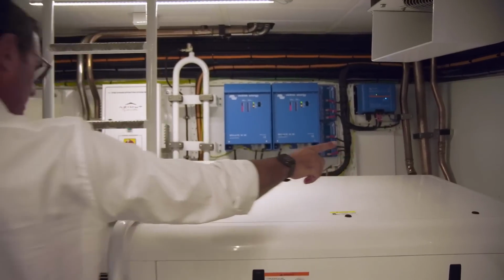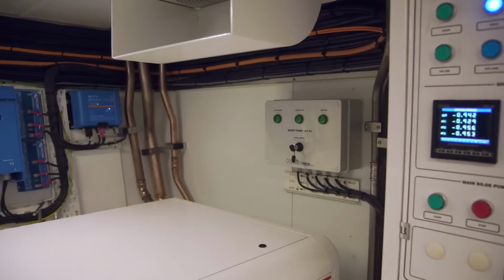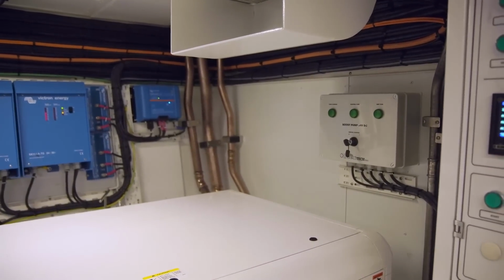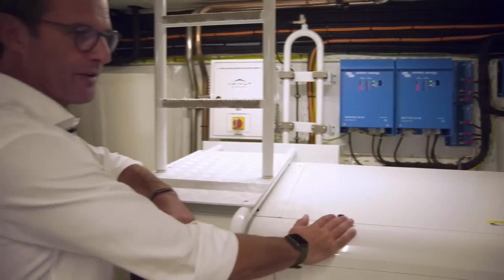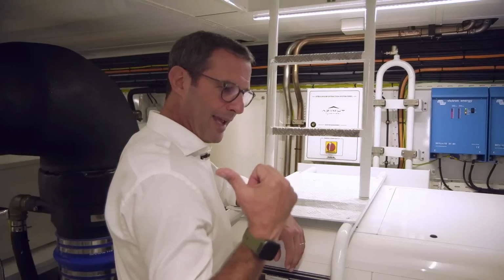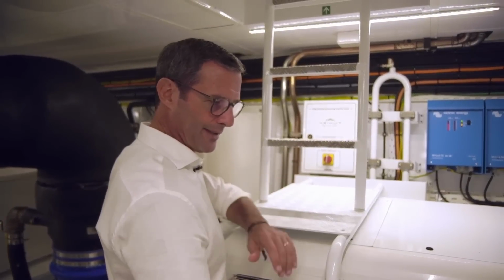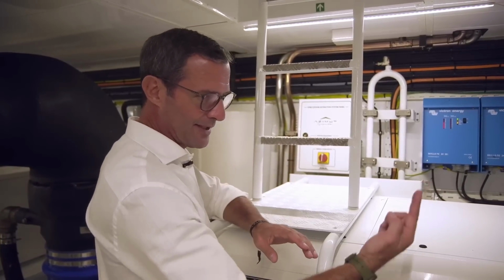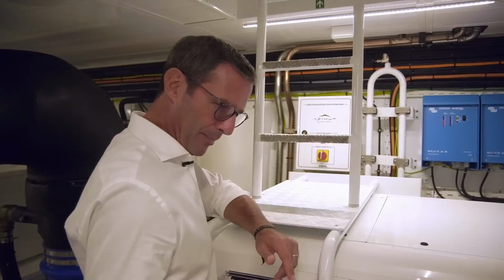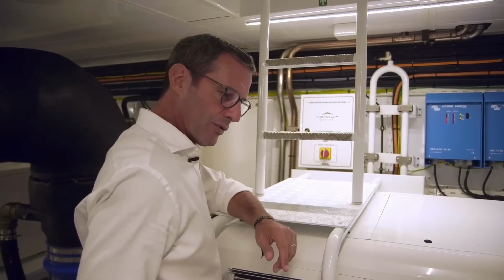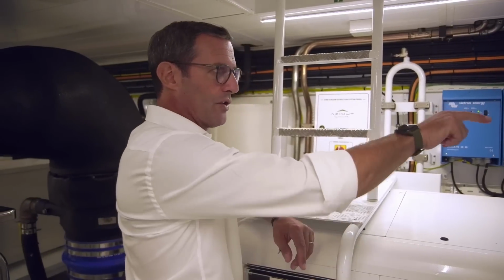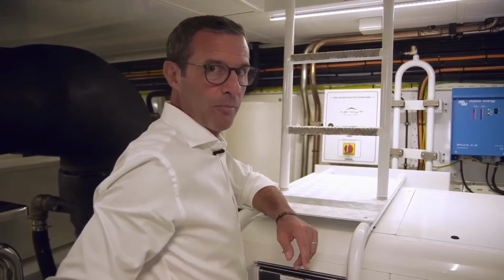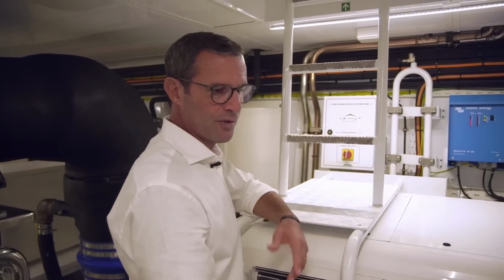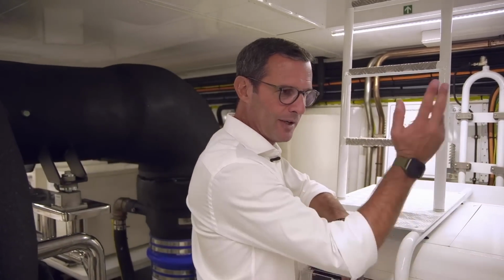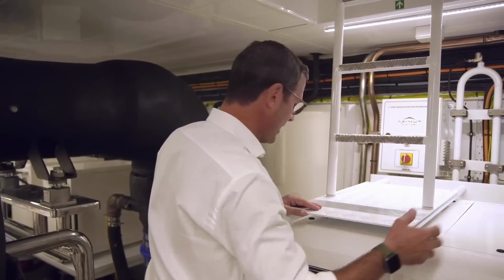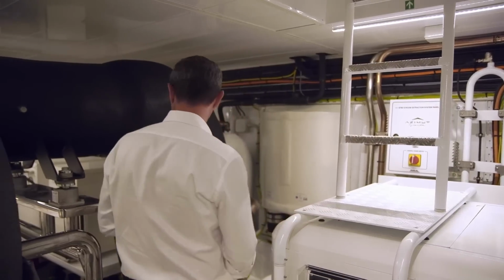Boost pump, right there - you've probably seen one on the other side as well. The boost pump is for fuel of the generator, in case the fuel tank is lower in height than the generator, and fluid doesn't tend to go uphill. So in case the pump of the generator doesn't have enough suction to take fuel from the fuel tank, you just turn that key and you have an additional pump which feeds fuel to the generator, so it doesn't have to make that much of an effort, and it comes on right away in case the system was drained.